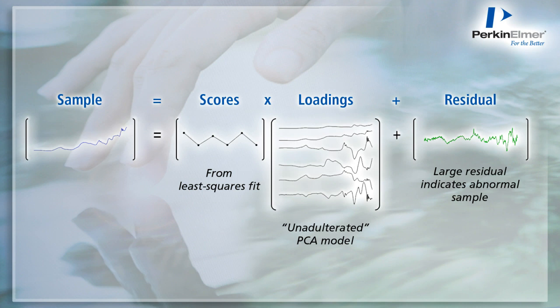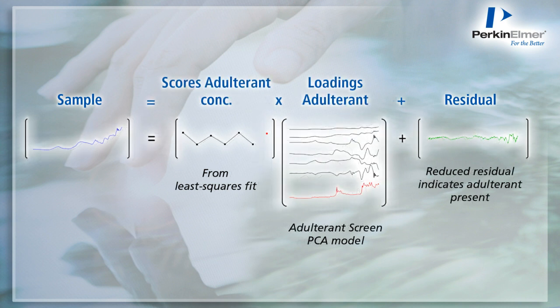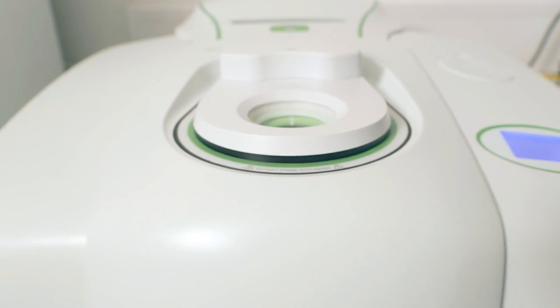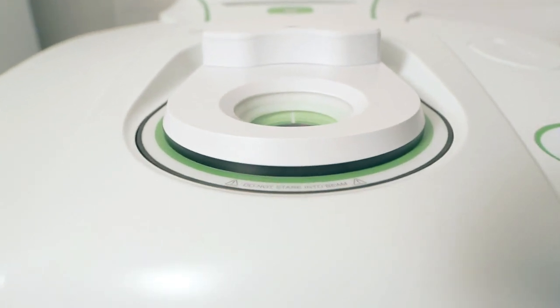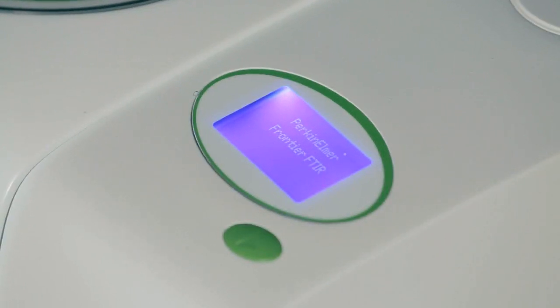Then we see how well the sample spectrum fits into this model. If it's significantly contaminated, there will very likely be a large residual. Next, the software runs through the library of adulterant spectra and includes each one into the model. If as we do so the fit to the sample spectrum greatly improves, that indicates that the adulterant may be present in the sample. The advantage of this approach is that we improve sensitivity by using the adulterant spectrum, but it doesn't require us to prepare a large number of standard samples for each adulterant, meaning we can cast the net much wider.